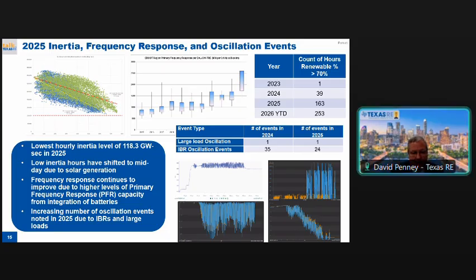The two charts on the right-hand side are both solar plants that started oscillating their megawatt output. One was during a high peak part of the day, and the other during a solar ramp-down period, which we detected through small frequency variations caused by the megawatt swings.